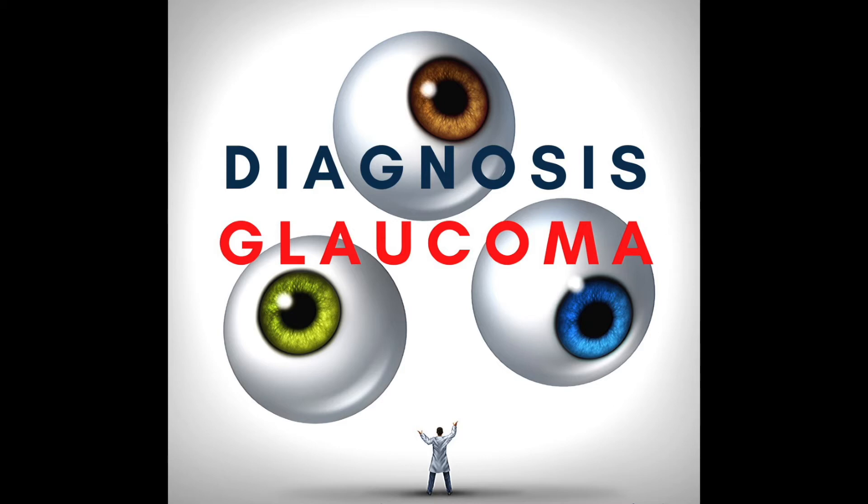How accurate is the iCare compared to other means of checking eye pressure? They have done several studies comparing the iCare to the standard, which is Goldman applanation tonometry. What they have found is that they're pretty similar. About 95% of patients will fall within about 4 to 5 millimeters of mercury difference between the Goldmann — the little blue light — and the iCare tonometer. Only about less than 2% of patients will have a difference greater than 7, which is a pretty big difference.